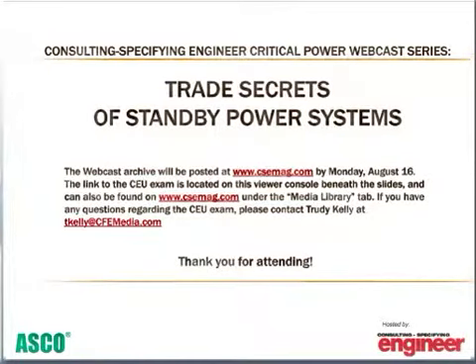Very good. The next question is going to go to Ken Lovorn. This one from David Pollock from BSEG LLC, and he's asking, who sets sound level requirements for installation and where can they be found? Ken. As far as I know, there's not any specific code requirements. Really the target is you need to not exceed the sound level of the ambient conditions under the worst case operating point. So if you're in the middle of the country and it's a rural area, at night it's going to be pretty quiet. And so if there's any chance of you disturbing anyone out there, you have to go with the worst case. If you're in the middle of an industrial complex and the sound level is 85 dB under normal circumstances, then you really don't need much attenuation. So it really is dependent on the environment and who you might disturb.